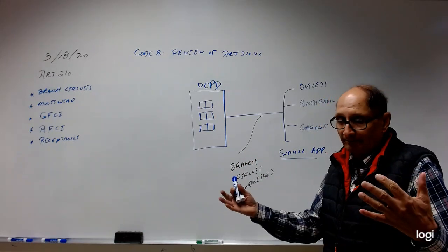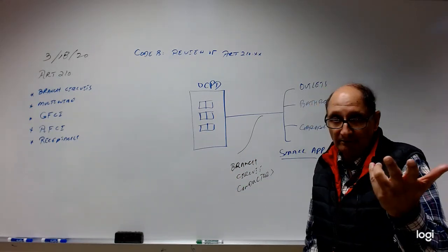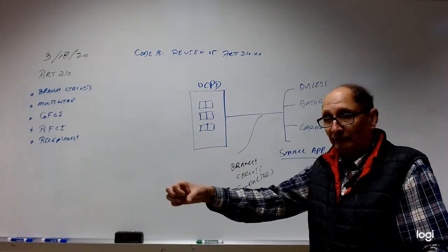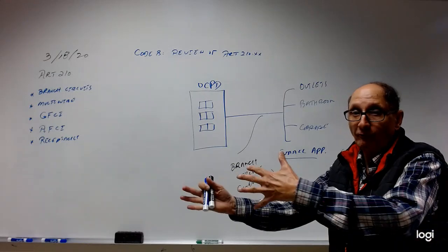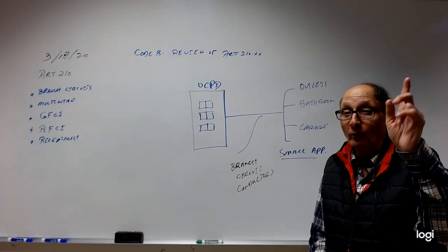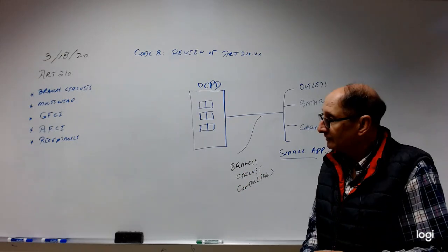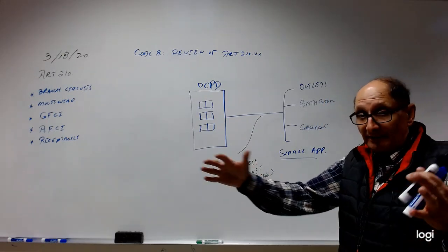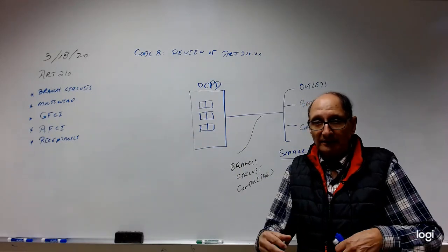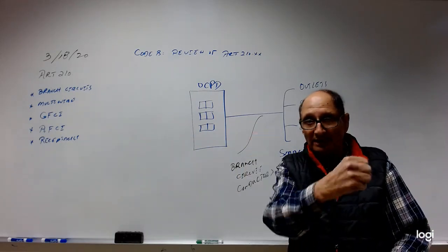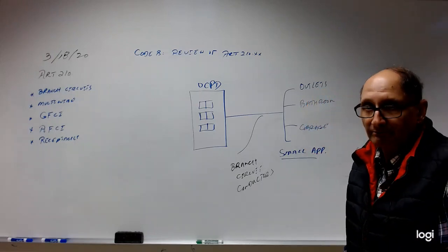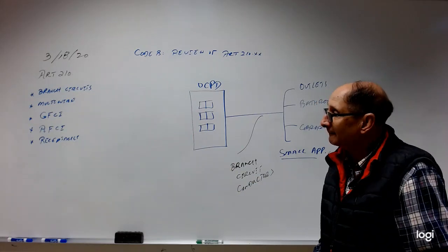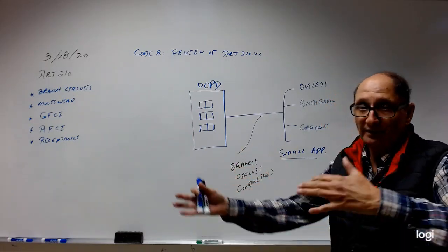And then we have countertop receptacles, again a 2-4 foot rule. You need a receptacle within 2 feet from the end of the countertop and then 4 feet thereafter, provided the wall space is 12 inches long. That's another requirement you have to keep in mind. And if there is any barrier in between, if there's a break, or no usable space, meaning any place where we cannot place receptacles, that's a no. So you start fresh from the other side and count 24 inches, 2 feet, and then go all the way.